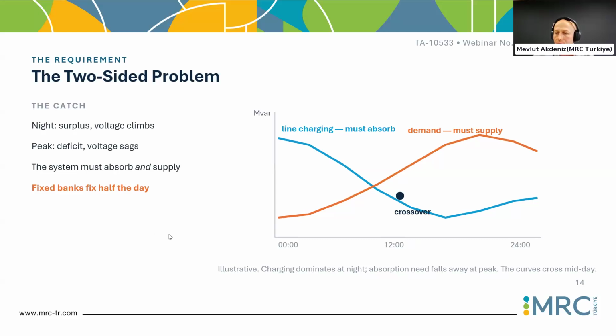And during the day peak hours, vice versa, we have a similar problem with negative voltage depression. With the absorption of too much active power, and also some reactive power, the line or the network can be loaded over the surge impedance loading. So there's a very primitive, basic but good indicator for the lines. Most of our TSO colleagues are aware of that. We have the natural loadings of the lines, also called surge impedance loading. So if the network is loaded above these values, we need reactive power support here. Or if the loading is less than this critical natural loading, we need some shunt compensation to absorb the excess reactive power at this point.